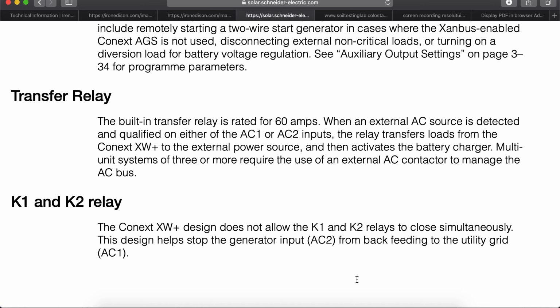This is an internal transfer relay. The built-in transfer relay is rated for 60 amps. When an external AC source is detected and qualified on either of the AC1 or AC2 inputs, the relay transfers loads from the XW Plus to the external power source. It stops inverting and uses that external AC input, and then, optionally, activates the battery charger.